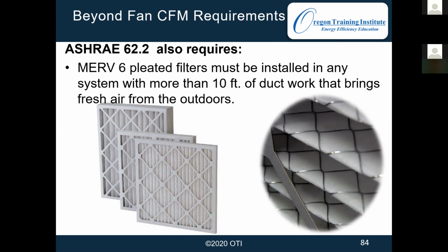How this was interpreted back in 2010 was, and this was no one in particular, it was the whole country, thought that this meant that every home that we went into that was forced air, we had to put a MERV6 filter in. That was later clarified. No, only if that furnace is bringing in fresh air from the outside.